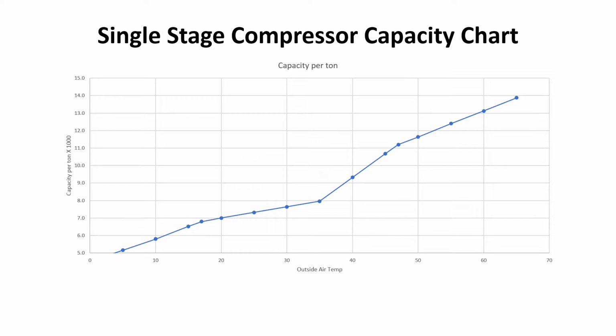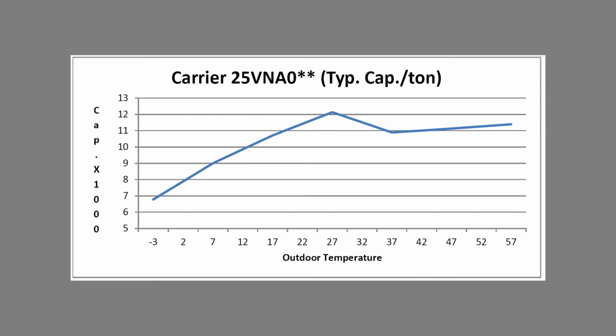The capacity per ton. So basically what we can see, sure enough, at 65 degrees, wow, we're above our full rated capacity. That's good news. By the time we get down to, say, 47 degrees, we're right at about 12,000 BTUs per rated ton, exactly where we'd be. And as we go down, we hit what's called the defrost knee, if you will, because at this temperature, you can make a lot of ice, and there's generally a dip in the capacity.